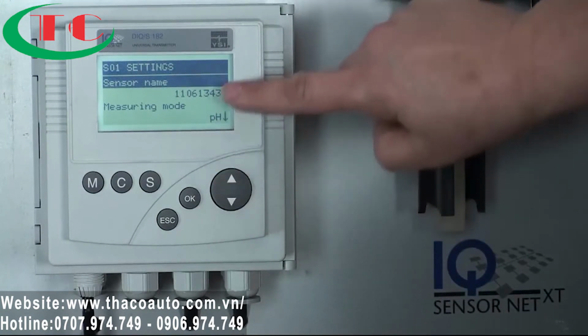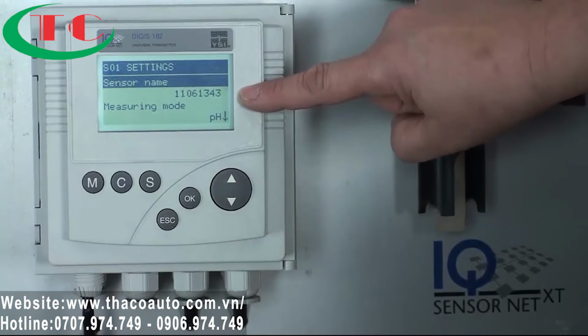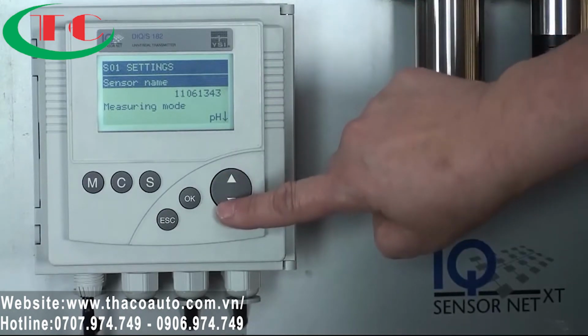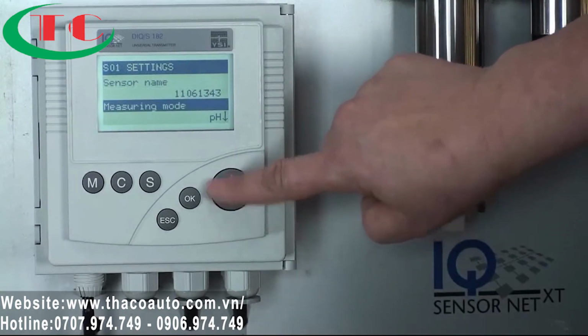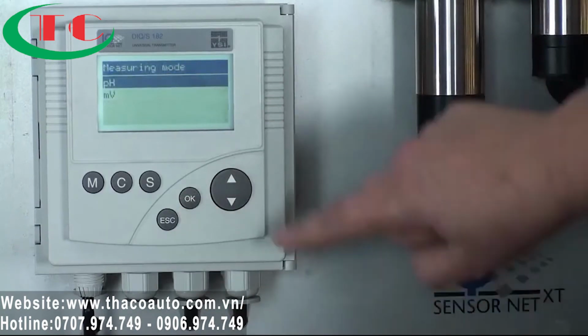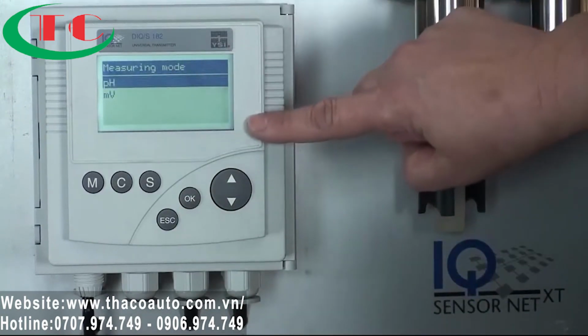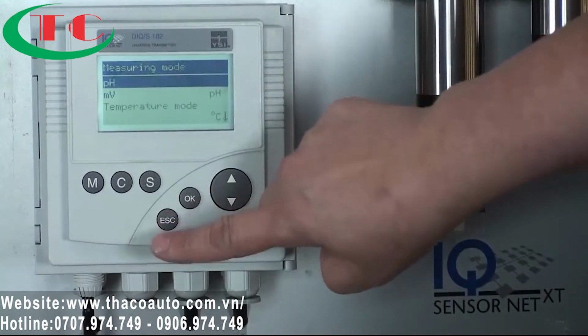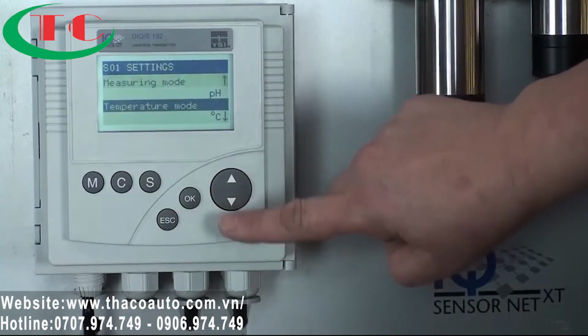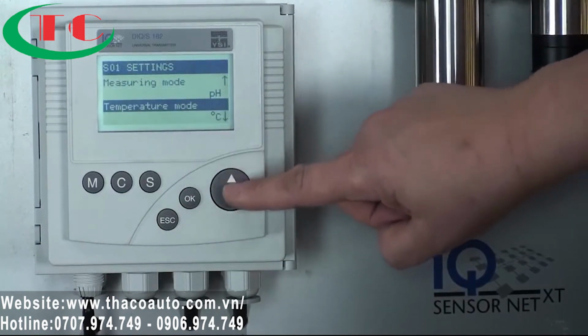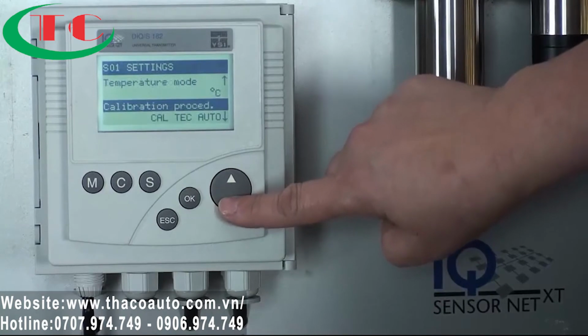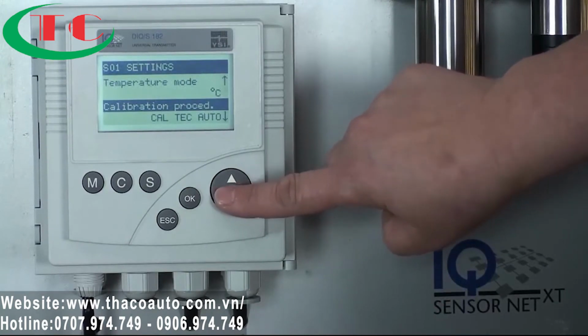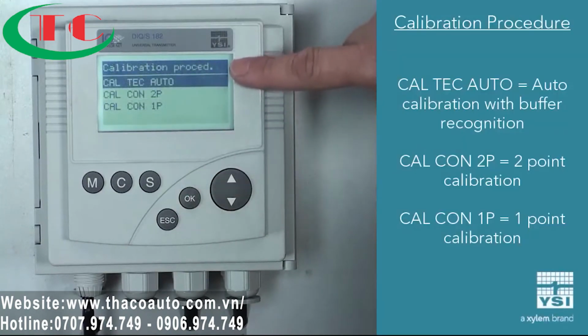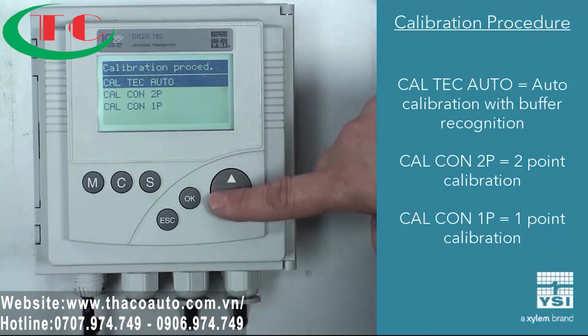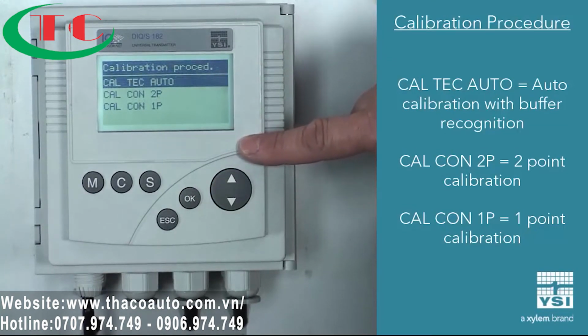So as you can see, it's giving me the sensor name, or in this case, it's giving me the serial number. If I go down to the measuring mode, for this sensor in particular I could choose either pH or millivolts, and I'll hit the escape button to go back one. Temperature, you can choose either Fahrenheit or Celsius. Calibration procedure, and you can choose CalTech Auto, which is what we would prefer. You can choose one of the others, CalCon 1 or CalCon 2.